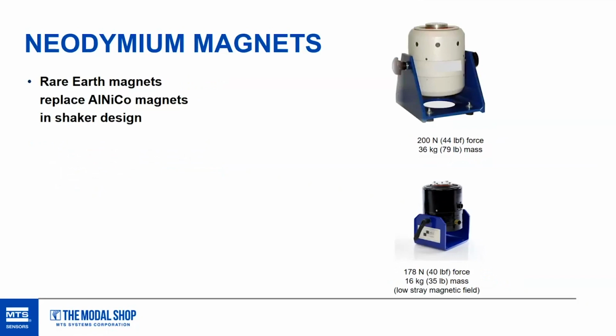So basically for any new design nowadays, we would prefer to use a neodymium magnet, or an electromagnet if it's a larger size shaker. But for the smaller shakers, definitely a neodymium magnet as the permanent magnet choice.